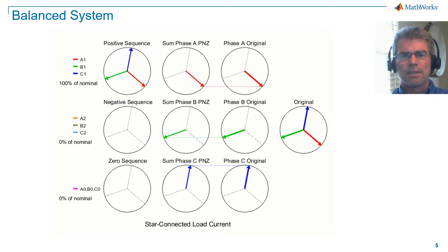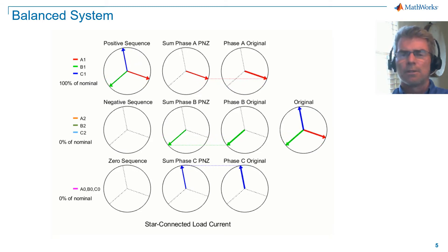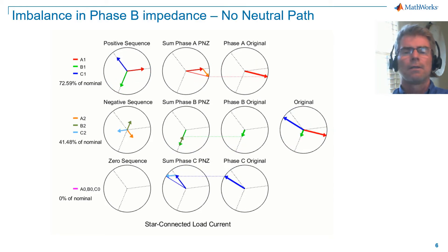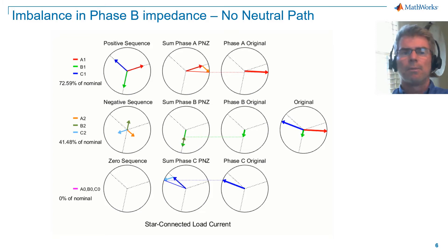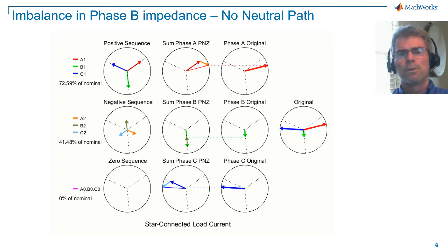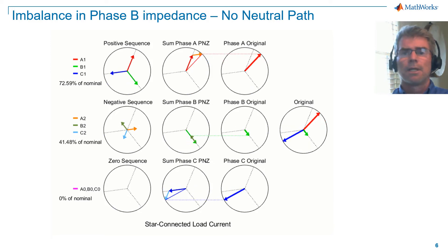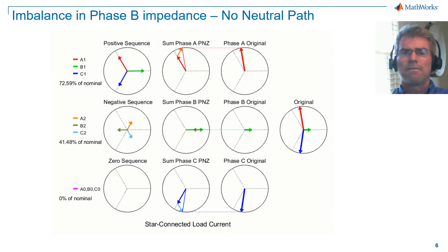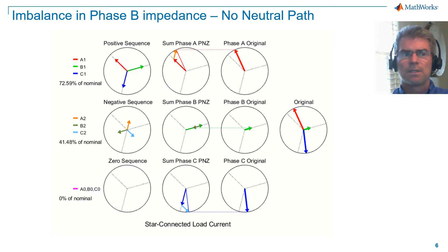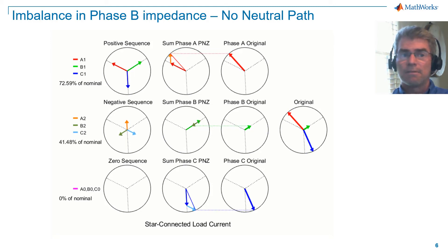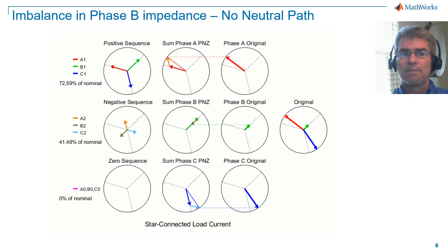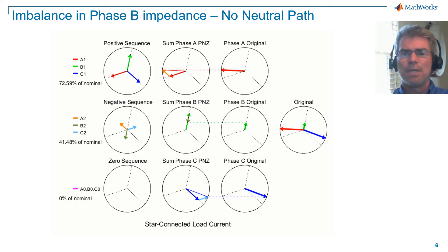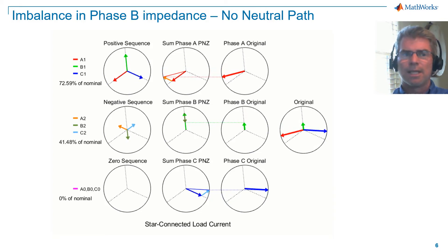Now let's take a look at an unbalanced system that has no neutral path. To imbalance the system, I'll increase the resistance in phase B of the system load. You can see in our left column that we now have a negative sequence. Also note that the positive sequence is reduced in magnitude. As this example has no ground or neutral path, we have no zero sequence current. Note that the phase ordering of the vectors in positive sequence is ABC — B lags phase A, and C lags phase B. In the negative sequence, the phase ordering of the vectors is ACB — C lags phase A, and B lags phase C.